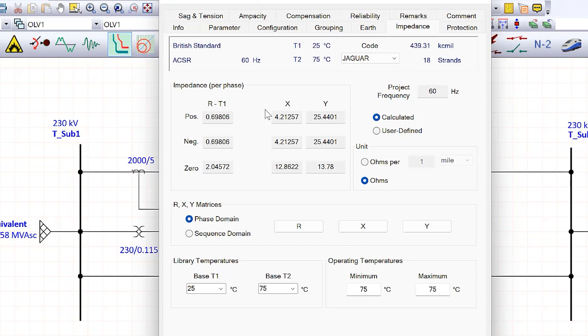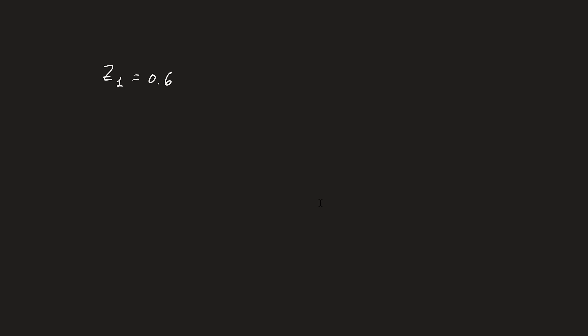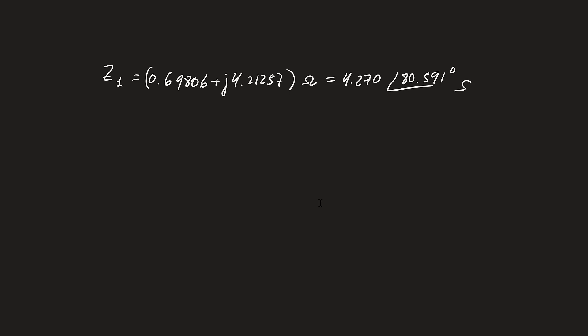We need to calculate the reaches in terms of the positive sequence impedance. Going to the notebook, Z1 — the positive sequence impedance — is 0.69806 + j4.21257 ohms. Converting to polar form, that equals 4.270 at an angle of 80.591 degrees, in primary ohms.